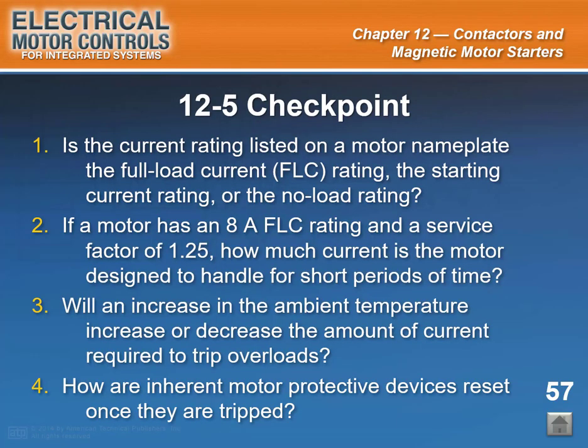Slide caption: 12-5 checkpoint. Is the current rating listed on a motor nameplate the full load current, known as FLC rating, the starting current rating, or the no-load rating? If a motor has an 8 amp FLC rating and a service factor of 1.25, how much current is the motor designed to handle for short periods of time? Will an increase in the ambient temperature increase or decrease the amount of current required to trip overloads? How are inherent motor protective devices reset once they are tripped?